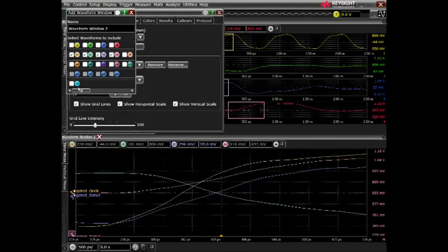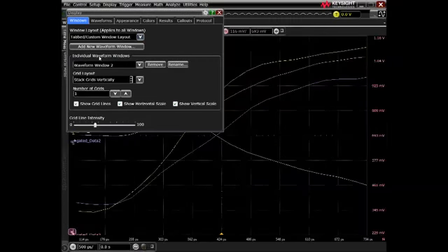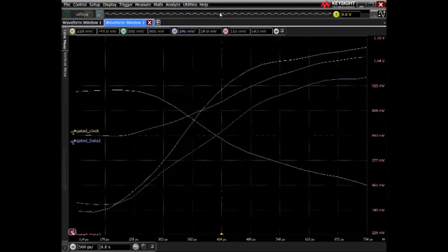Now, I'm only using four functions, but you'll notice that we've got a lot more to play with. If you wanted up to 16 of these different gated areas, you can do it. Works great. All right, so I've done that. Now what you'll see is I've got these stacked. I've got my original waveforms on top and my gated areas on the bottom. Again, I really don't want to see these, so I'm going to push them to a different tabbed area. Cool. Now here's just the gated sections of those waveforms.